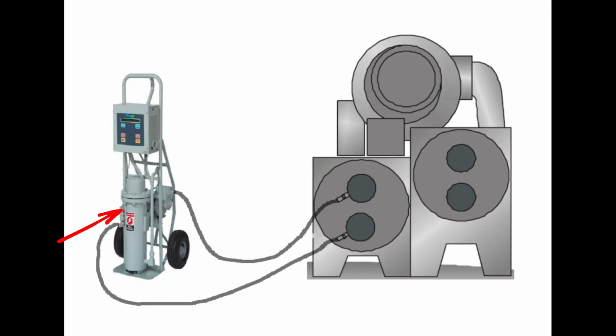If you could build something like this, you quite literally just take a barrel, find a way to mount and isolate, because you've got to think all this is going to be pressurized, okay? So bear in mind, this is a pressurized loop on either side. Well, your condenser may not be pressurized in some cases, but you're dealing with a pressurized water system. So it can't be just an open vat, like an open barrel. But if you can get a heater in it and you can hook up a little transfer pump, and you're willing to manually monitor the pressure to make sure you don't overpressurize and such, by all means, there's ways to build these yourself, or you can just go get RefTech's set up.